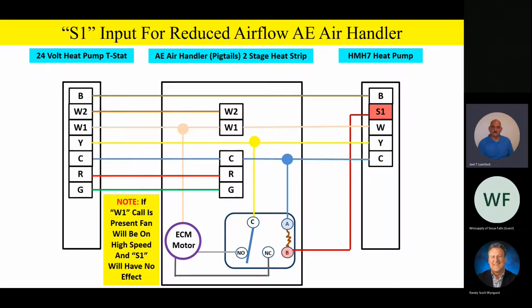So in this example here, if I get a W1 call, let's say I'm on a normally open contact and I'm in low airflow, for instance, and then all of a sudden I get a W1 auxiliary heat call. What's going to happen is it's going to drive that fan to that high speed tap that we hooked up for W1 for an auxiliary heat call. And even though it's calling for lower airflow, if it sees a higher speed command, it'll go ahead and take that command. We call that airflow priority on our ECM type of motors.